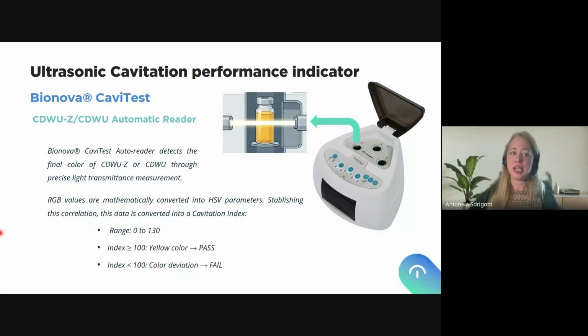How it works. This auto reader detects the final color of the indicators through precise light transmittance measurement. And these RGB, or red, green, blue values, are mathematically converted into HSV parameters: hue, saturation, and value, or brightness. And we establish a correlation that converts these values into a cavitation index that goes from 0 to 130. When the index is equal to or more than 100, it is a yellow color, a pass result. And when this cavitation index is less than 100, there's a color deviation that could go through different shades of light green that can be confused with yellow, until 0, which is actually the initial blue color.